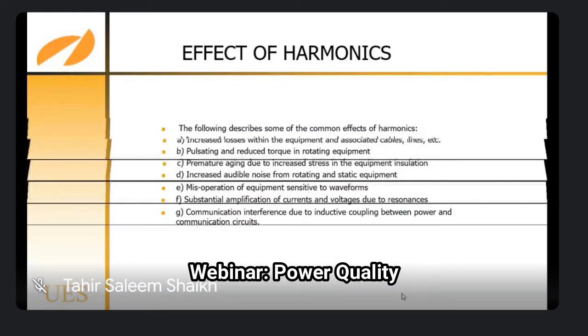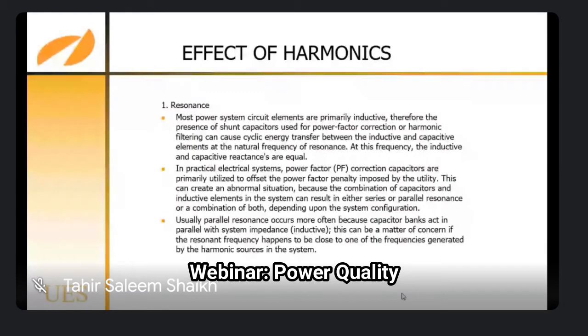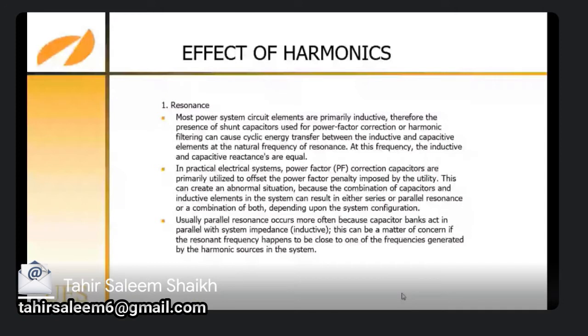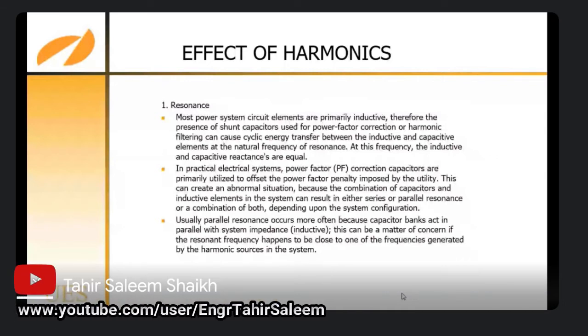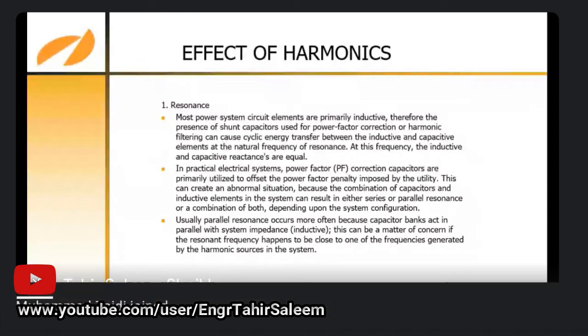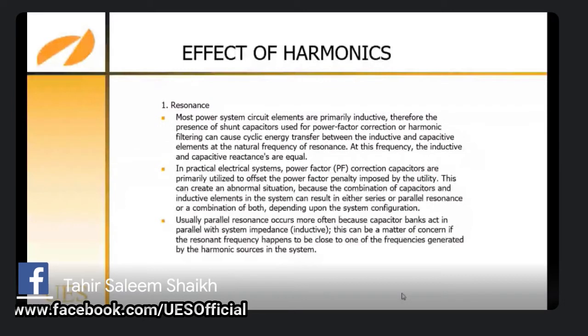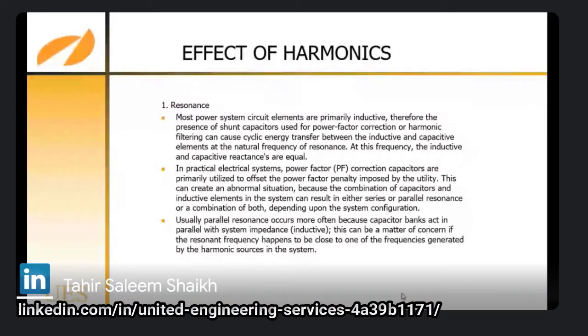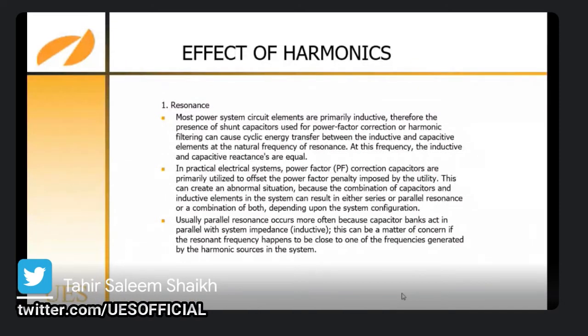Resonance: most power system circuit elements are primarily inductive, therefore the presence of shunt capacitors used for power factor correction or harmonic filtering can cause cyclic energy transfer between the inductive and capacitive elements at the natural frequency of resonance. At this frequency, the inductive and capacitive reactance are equal. In a practical electrical system, power factor correction capacitors are primarily utilized to offset the power factor penalty imposed by the utility. We all know that.